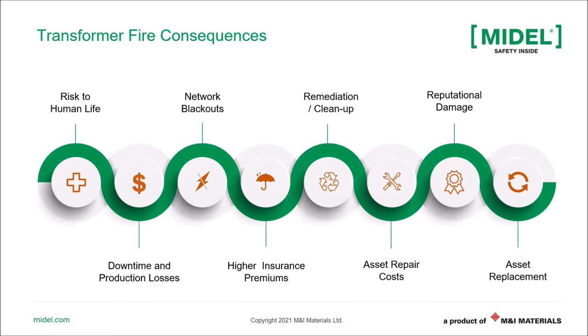FM Global, the global insurer, reported that in the past 10 years over 14% of losses were due to transformer fires. So there are many case studies here as to what can happen when transformer fires occur. Just to give you some instances, there are case studies where transformer fires have taken place and businesses have not been able to operate in the same location for over 6 months due to the smoke created, or the fire was so severe that it burnt down the building or something around the building which was sensitive.